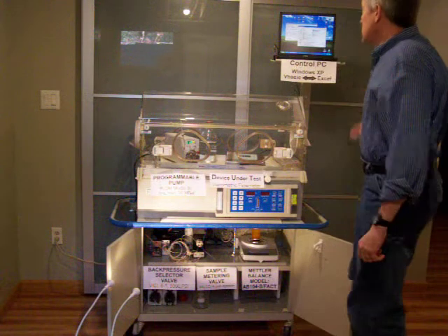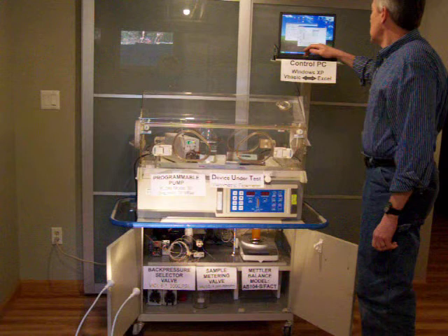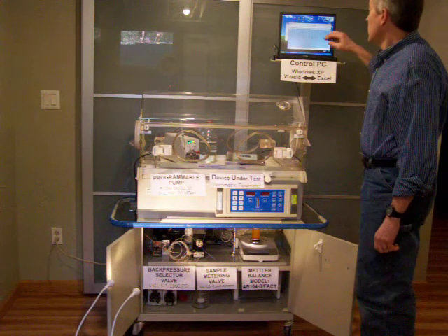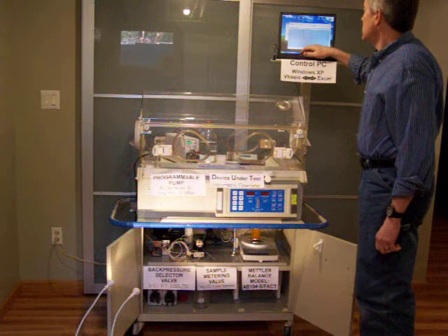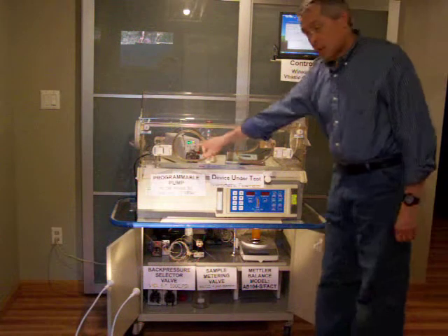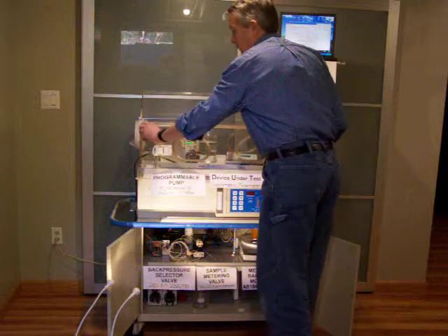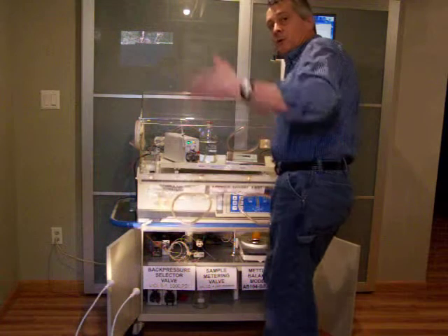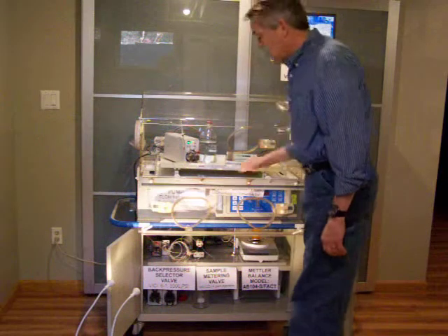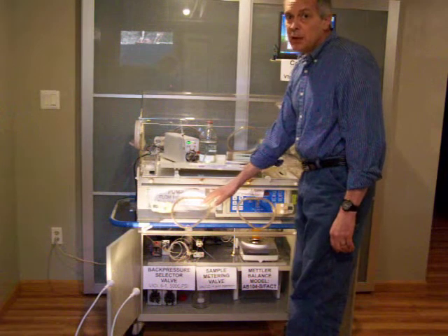So, to start collection here, we select the input file for the script. The flow collection program then selects the various flow rates as you progress through the script on the pump, and allows the flow rate to stabilize for a given period of time.